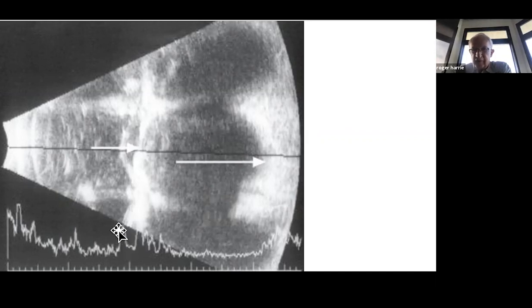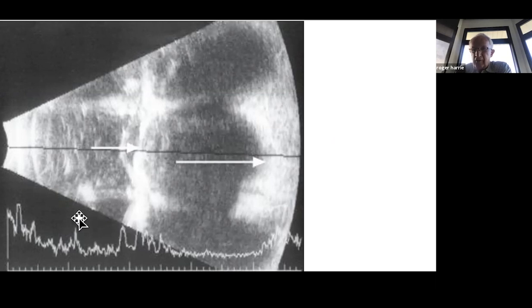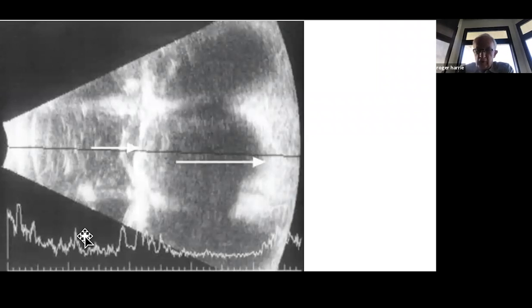For tumor diagnosis, the vector A-scan gives a rough idea of surface and internal reflectivity — high or low. However, the real diagnostic criteria established by Dr. Ossoinig require a true freestanding A-scan. If budget allows, a separate diagnostic A-scan with its own B-scan and high-frequency probe is always recommended over relying solely on the vector A-scan.